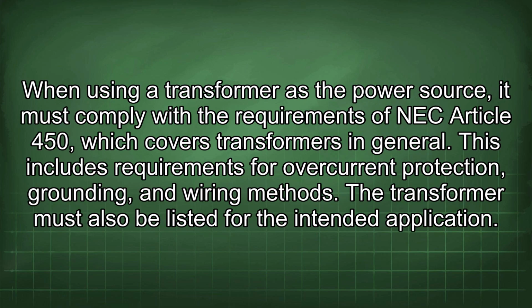When using a transformer as a power source, it must comply with the requirements of NEC Article 450, which covers transformers in general. This includes requirements for overcurrent protection, grounding, and wiring methods. The transformer must also be listed for the intended application.